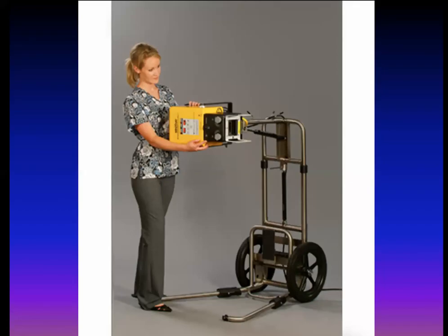And this is a picture of a mobile X-ray unit, so you can see it's quite a bit smaller, easy to move around. It has some wheels here, pretty stable structure. This is the X-ray source here, so the X-ray is going to come out of here. In this case, they would have to put the cassette on the other side of the patient. So the X-ray is going to come out, go through the patient, and then hit the film. So there's definitely some challenges to doing good work, but if you have a diligent technologist, they can certainly do a good job with it.